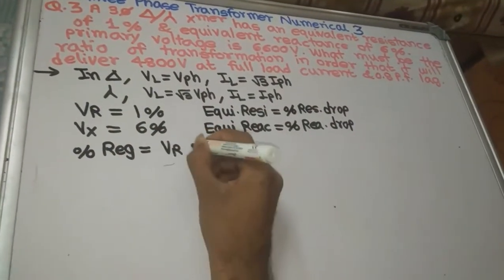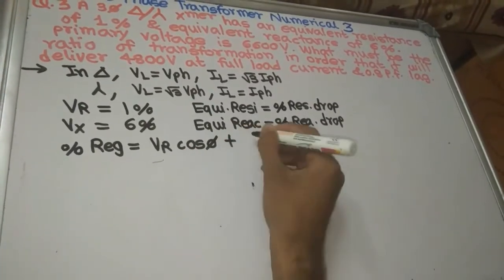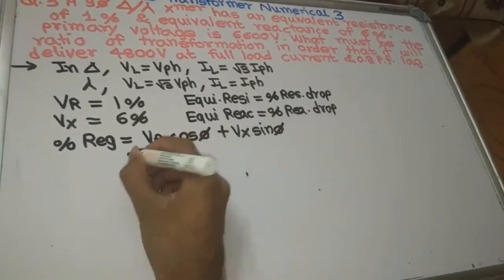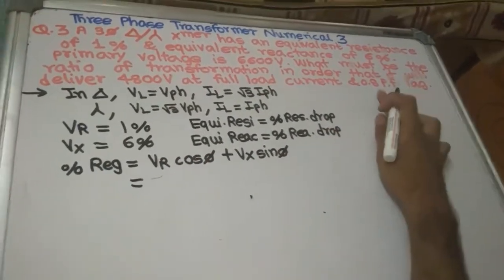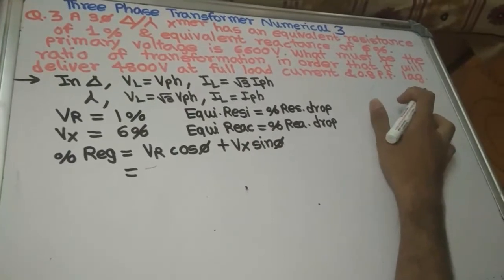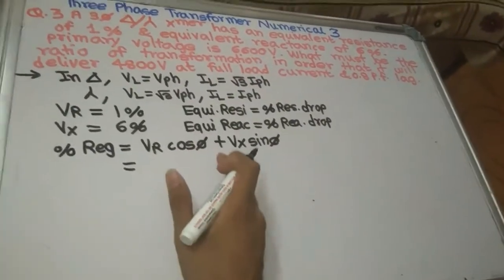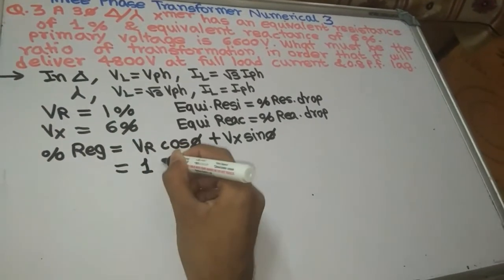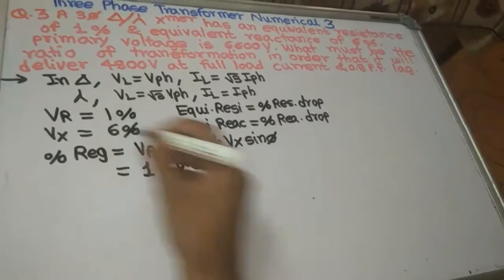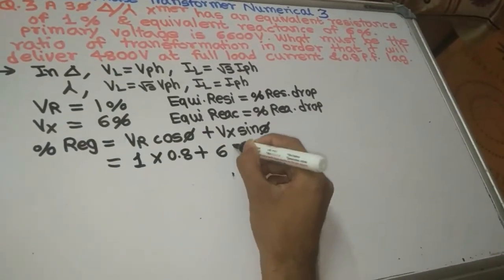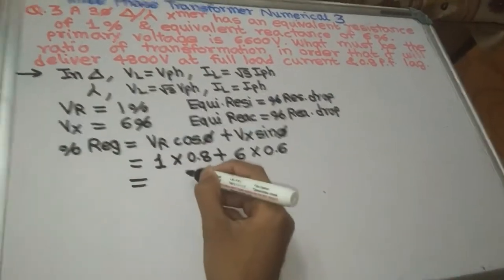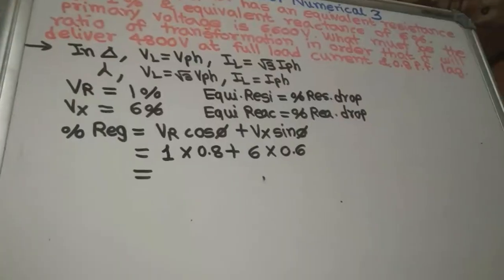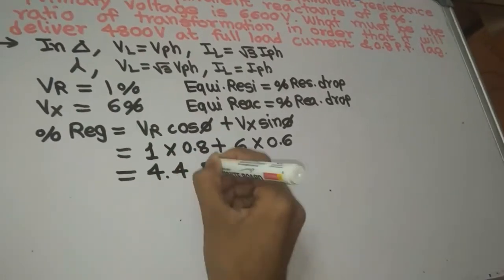The percentage regulation formula is: VR·cosφ + VX·sinφ. They said 0.8 power factor lagging, so we use the plus sign (for leading it would be minus). VR = 1, cosφ = 0.8, VX = 6, sinφ = 0.6. So percentage regulation = 1×0.8 + 6×0.6 = 4.4%.